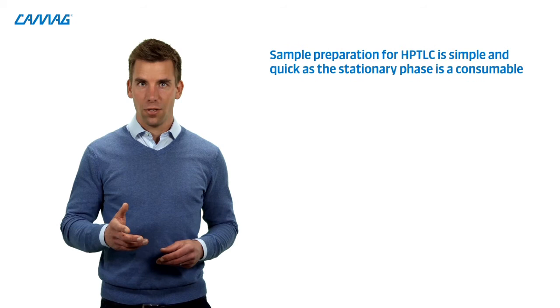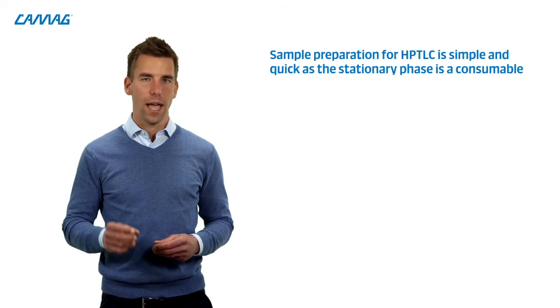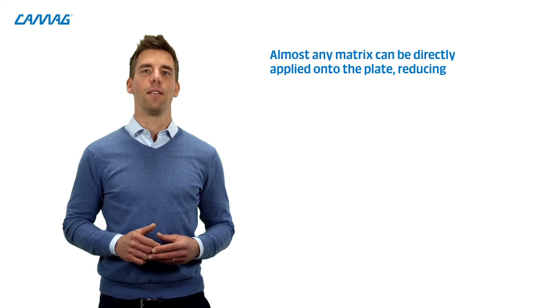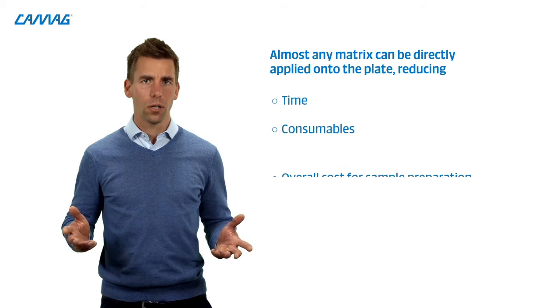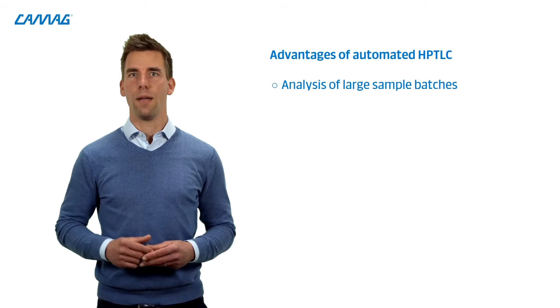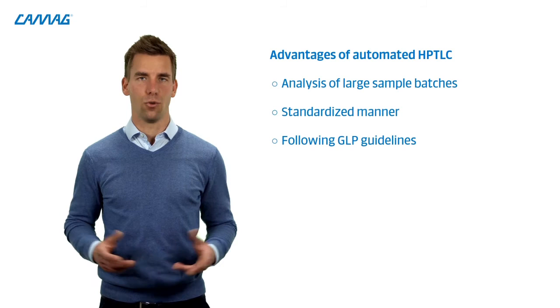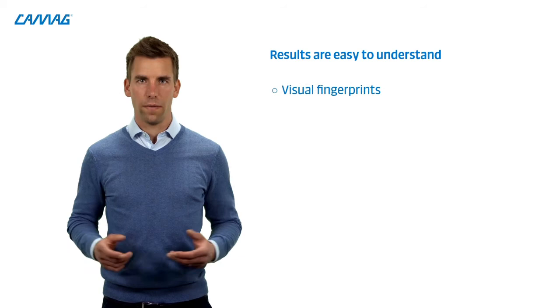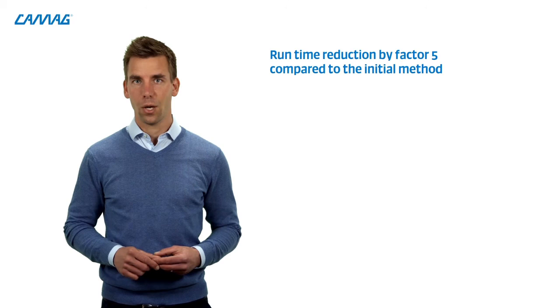The sample preparation for HPTLC is quick and simple. Because the stationary phase, the HPTLC plate is the consumable. Almost any matrix can be directly applied onto the plate, which reduces time, consumables and the overall cost for sample preparation. Through automation, we can analyze large sample batches in a standardized manner following good laboratory practice guidelines, GLP. The results are easy to understand through the visual fingerprints, plus the according quantification profiles. With the new method, the sample runtime was reduced by factor 5 when using the sequence mode on the HPTLC Pro compared to the initial method.